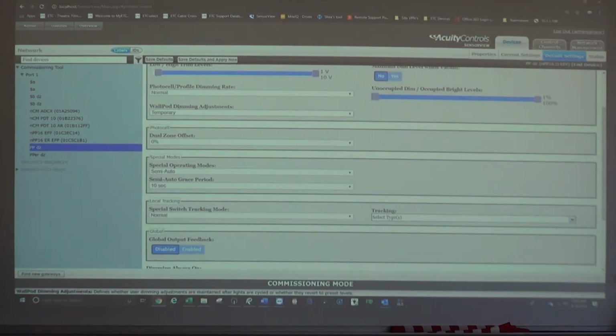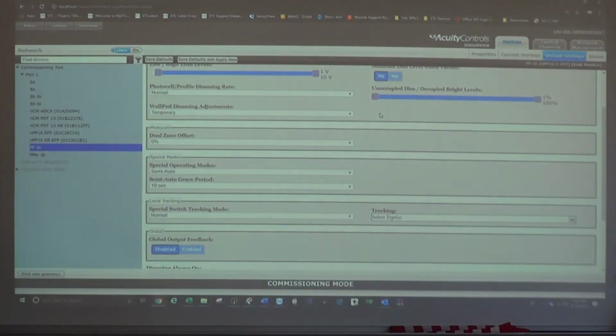Yes, we did change this. There's also a setting called wall pod dimming adjustments that every power pack has. In photocell zones, they're all set to temporary, meaning this zone doesn't apply since there isn't a dimming switch. But if you're in a space with a dimming switch and you dim down to 50%, then shut off and turn it back on, the lights will come back on to its occupied bright level, which is set to 100% right here.